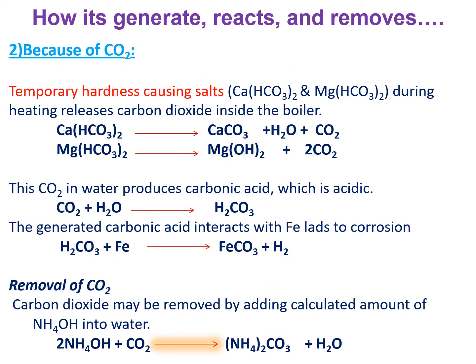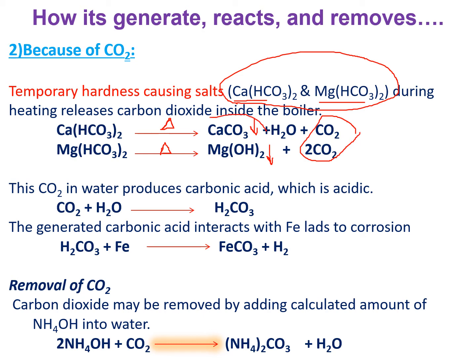Next is CO2: how is it generated in the water and how does it interact with the boiler material? If the boiler feed water contains temporary hardness-causing salts — calcium bicarbonate and magnesium bicarbonate — during steam generation at high temperatures, these salts undergo decomposition. Calcium bicarbonate precipitates as calcium carbonate and magnesium bicarbonate precipitates as magnesium hydroxide, but in this process CO2 gas is released. Because of this, scale or sludge is formed, and because of the CO2 gas, boiler corrosion occurs.